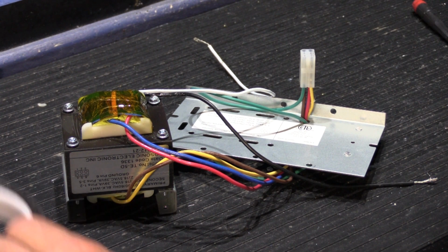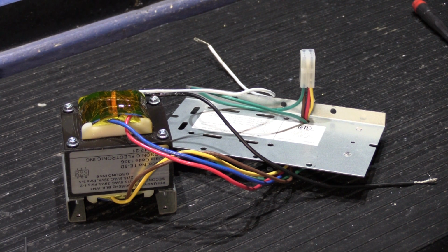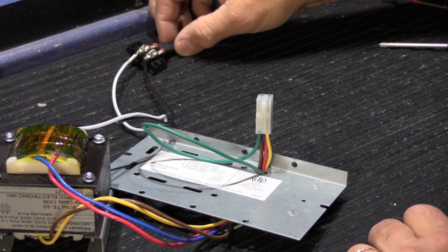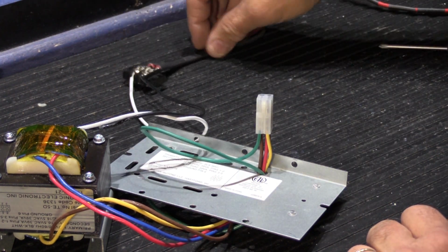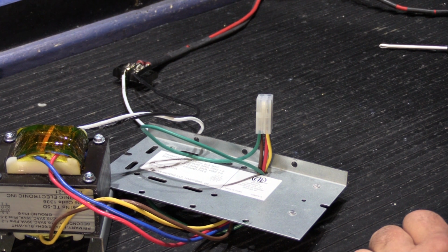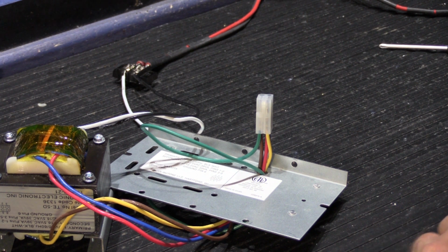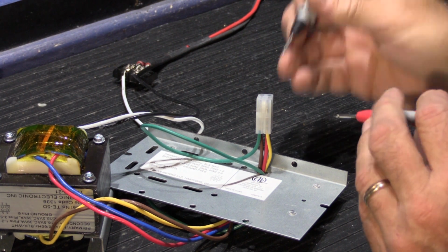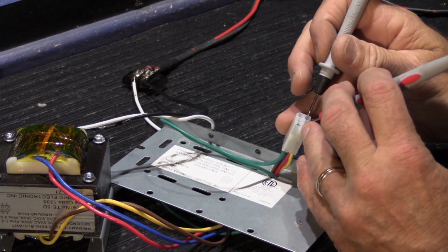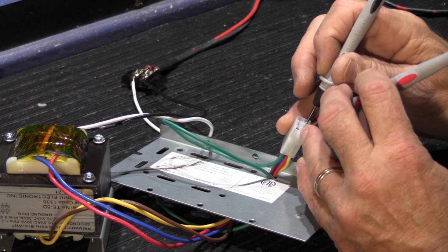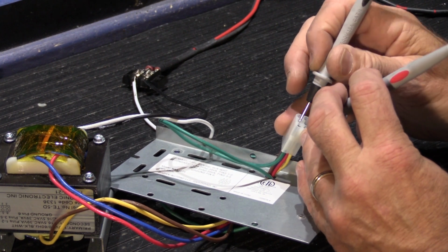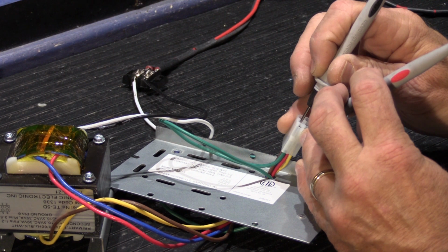So now the next step is to verify we've solved the problem and the transformer is good. Let's power it up and see what we have. I've got the transformer wired up on my bench power supply, which is an AC power supply set to 114.5 volts, which is fine. We'll flip on the switch and see if we have any sparks or flames. No, apparently not. We'll measure our outputs: blue and red give 17.1 volts, and brown and yellow give 17.1 volts.